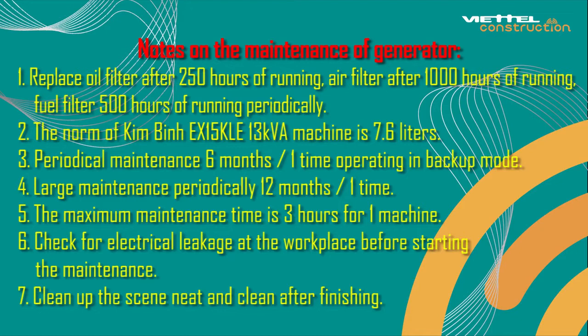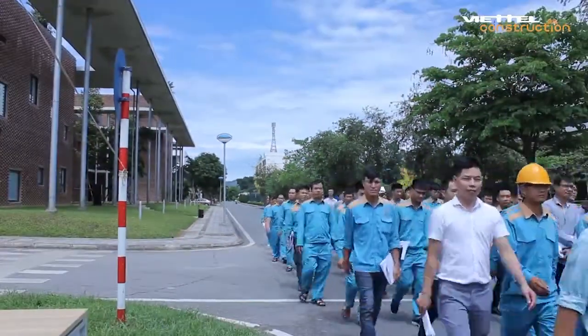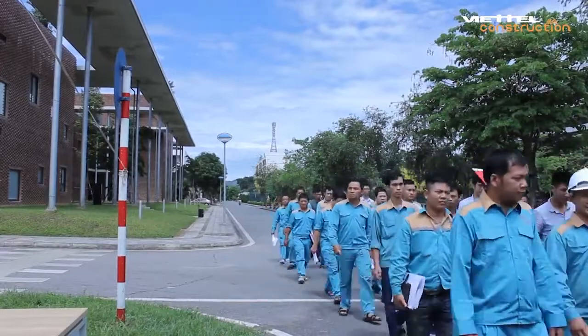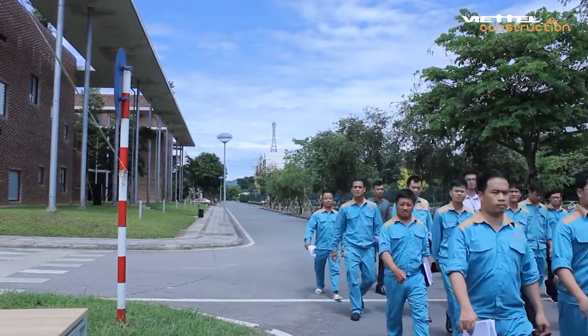3. Periodical maintenance 6 months, 1 time operating in backup mode. 4. Large maintenance periodically 12 months, 1 time. 5. The maximum maintenance time is 3 hours for one machine. 6. Check for electrical leakage at the workplace before starting the maintenance. 7. Clean up the scene neat and clean after finishing. Above are all steps for maintenance of the diesel generator by Kim Binh EX15KLE 13 kVA.